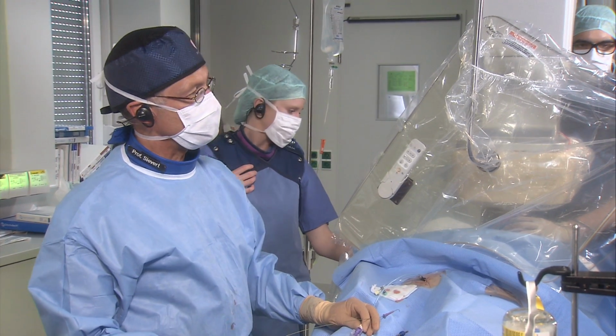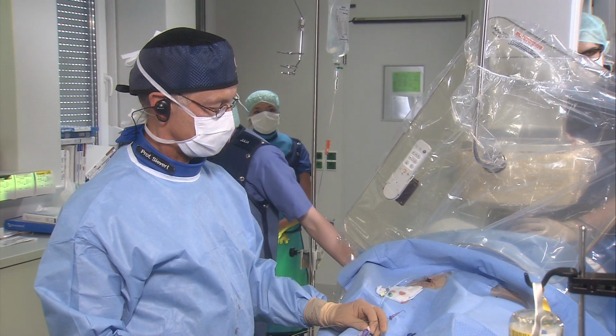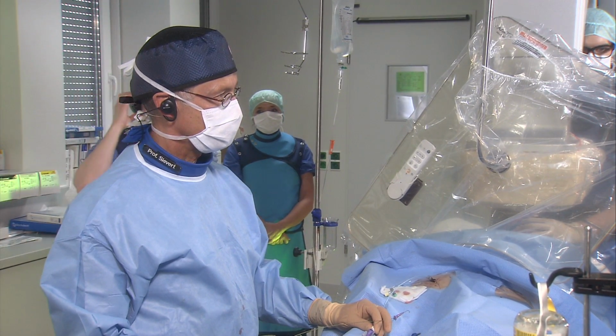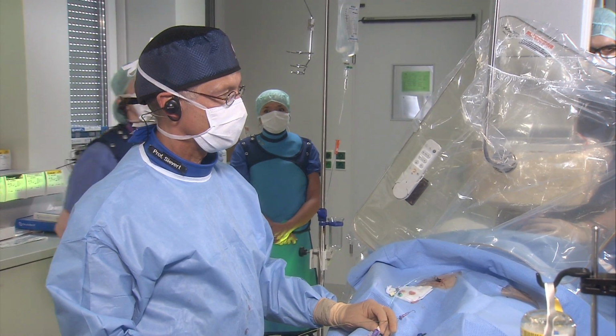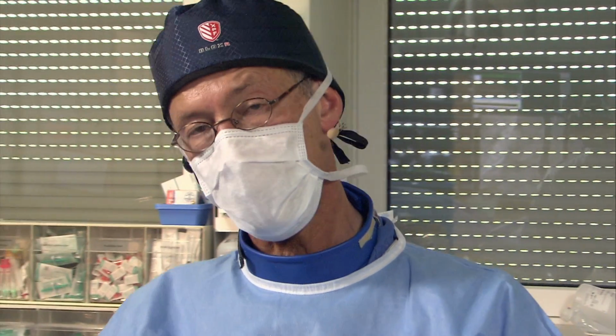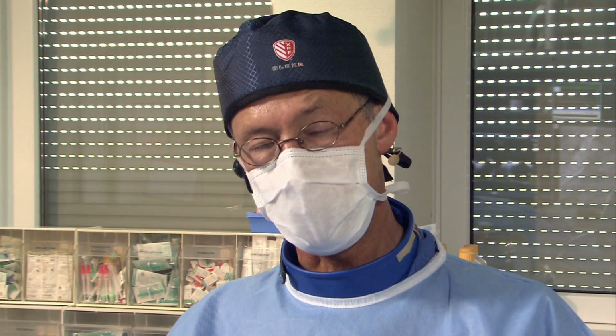Do you mean deformation during deployment or afterwards? During. Are you talking about Cobra? Well, Cobra head in the left side, specifically? Okay, so Cobra phenomenon, for those of you not aware of that, is a deformation of the, let's say, Amplatzer type devices, which occurs especially if you have a big sheath. That means an oversized sheath, and that may cause this configuration. And the only thing you can do when you see this is to pull out the device and reload it and re-advance it again, and most often then it works. It's caused by entangling of the wires of the device.